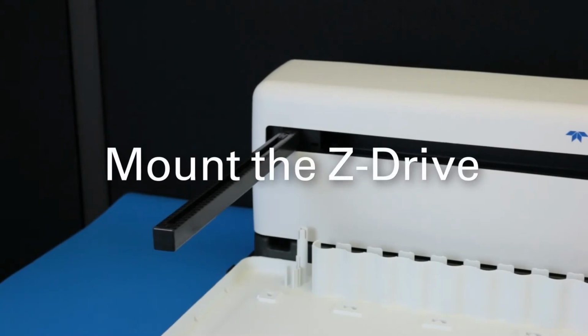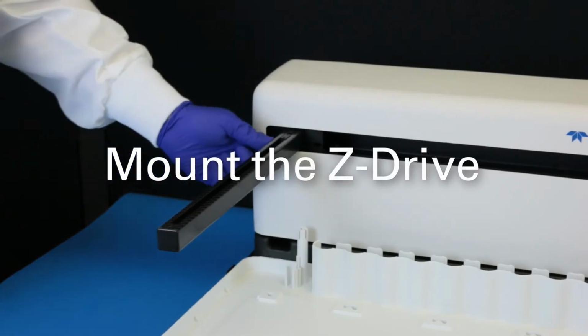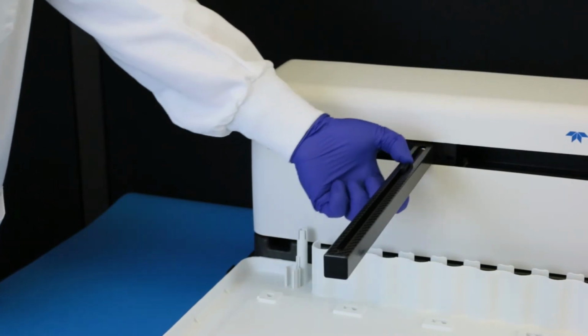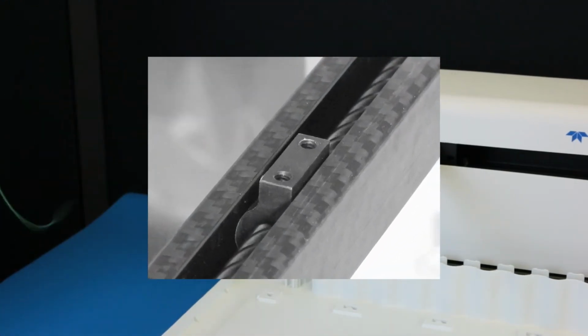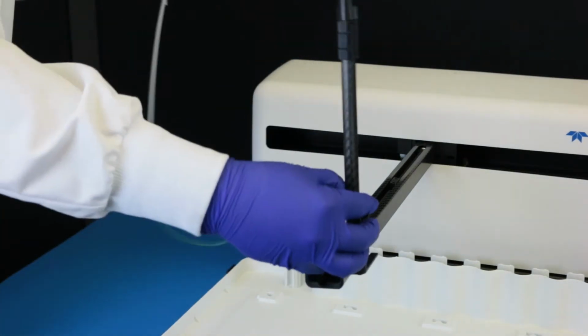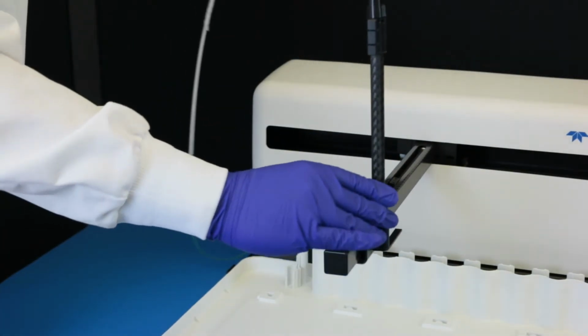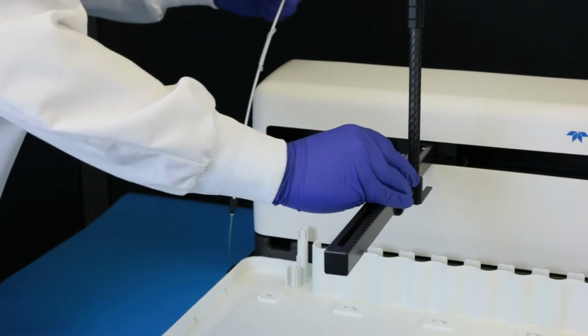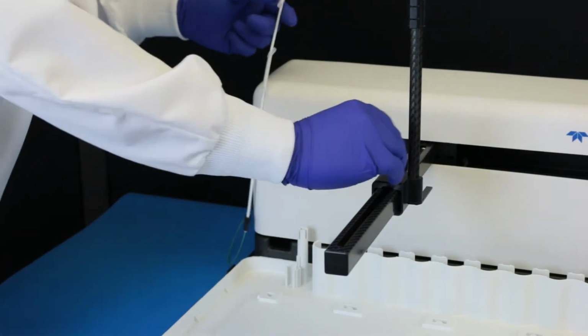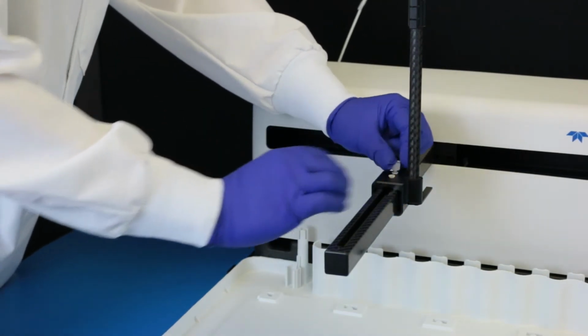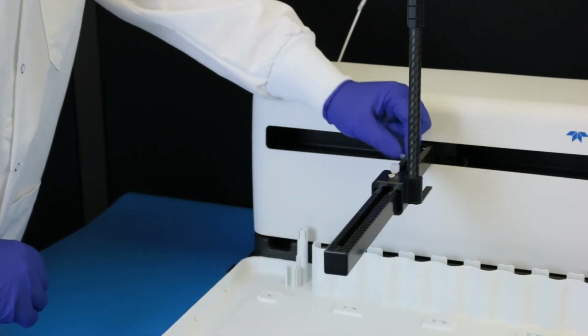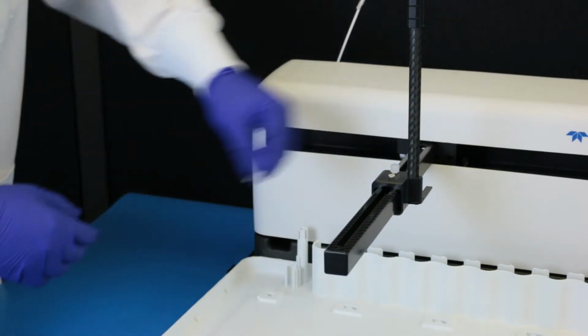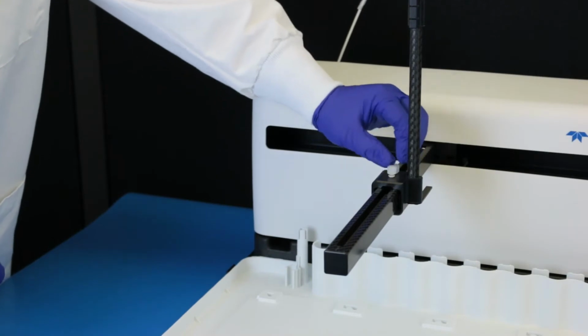To mount the Z drive, find the Z-axis carriage on the arm of the autosampler. The Z drive will be attached to this carriage. Slide the Z drive onto the arm until the two holes align with the matching holes in the carriage. Secure the Z drive to the carriage using the two thumb screws. Tighten the thumb screws using your fingers.